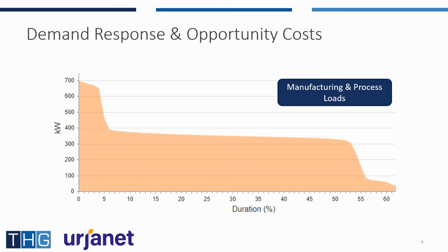Last but not least, a manufacturing site where we helped identify an unintentional overlap in their different operating lines. Eliminating this overlap during 6% of the hours of the month decreased their peak demand by over 40%. I only show you these examples to demonstrate again how a small percentage of hours of the month has the ability to drive a large portion of total costs.